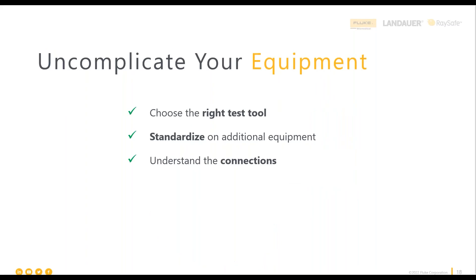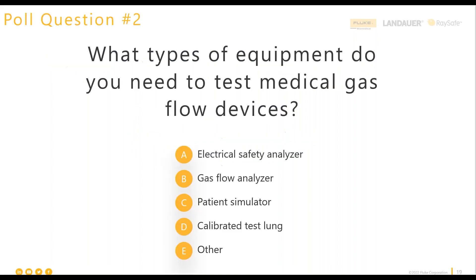To uncomplicate your test equipment, you need to get three things right: first, choose the right test equipment; second, standardize all of the equipment needed; and third, understand and document your connections because they are different from model to model. Before we jump into those three points, here's our next poll question: what types of equipment do you need to test medical gas flow devices? A) electrical safety analyzer, B) gas flow analyzer, C) patient simulator, D) calibrated test lung, E) other.